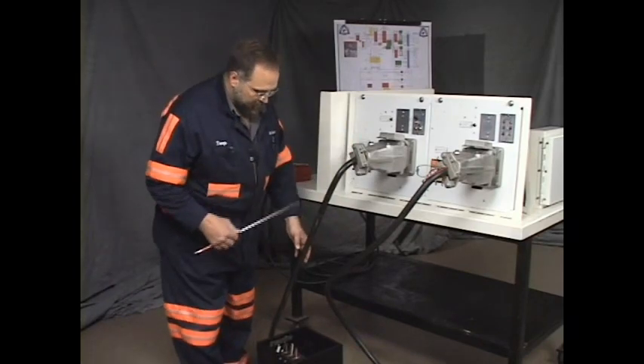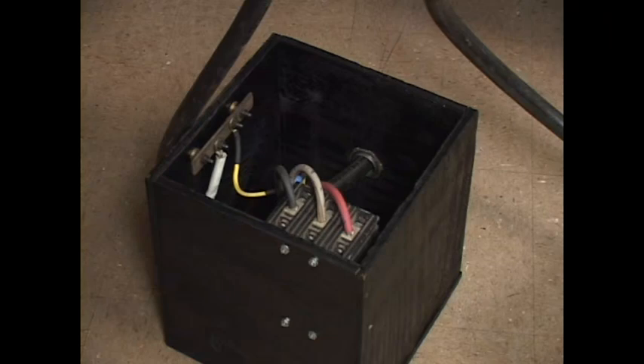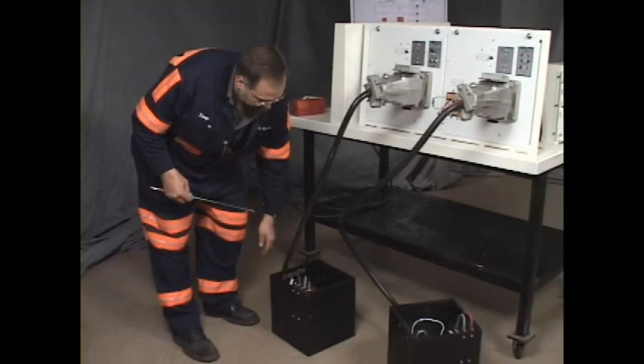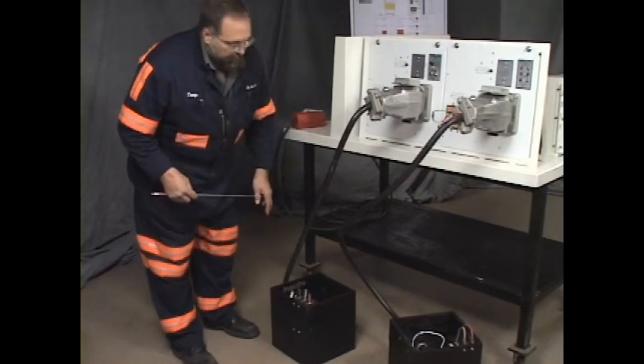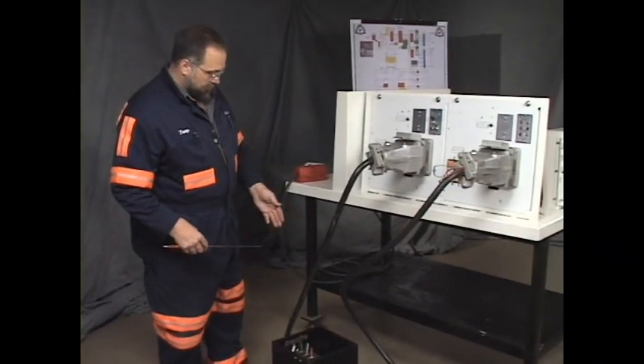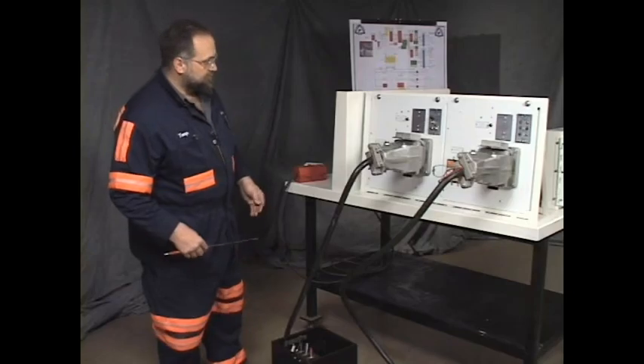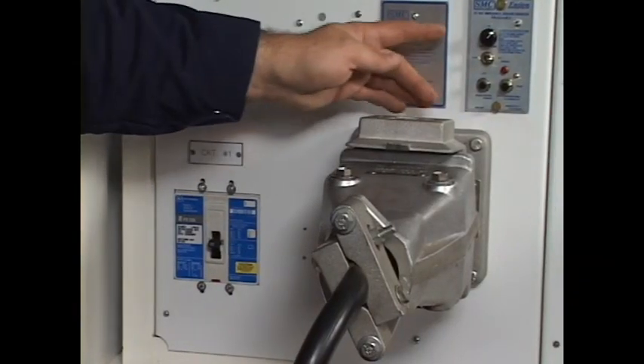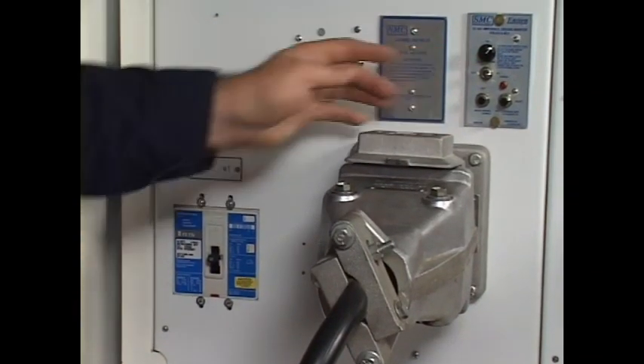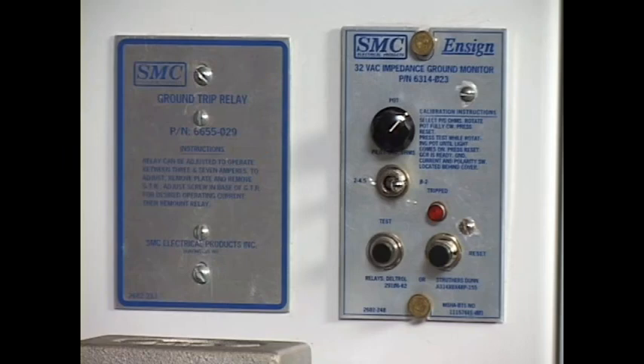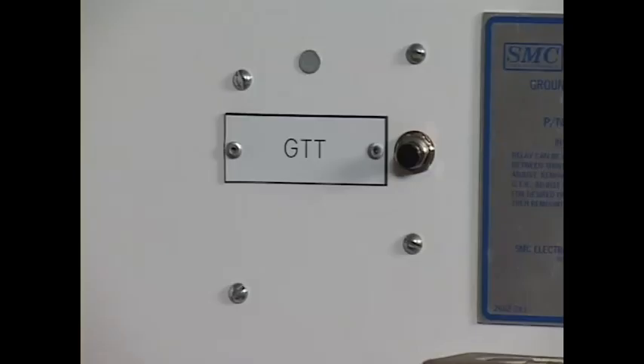to the machine. We use these plywood boxes here, as we spoke of earlier, to symbolize a machine. It has a machine breaker and a grounding bus for the ground and monitor to be hooked up to inside the machine. This is the ground monitor unit. It's labeled on the print as GCS1, Ground Check System 1. This is the ground trip test switch. You would operate this switch to test the ground trip circuit.